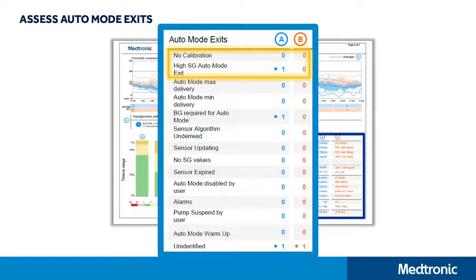Next, we want to take a look at auto mode exits. As a patient, auto mode exits can be frustrating, and we want to decrease, if not completely eliminate, auto mode exits. The 2 most common reasons for auto mode exits are 1, no calibration, and 2, high sensor glucose auto mode exit. These go back to the ABCs. No calibration, we recommend that they calibrate 3 times a day. High sensor glucose auto mode exit, we go back to the ABCs.